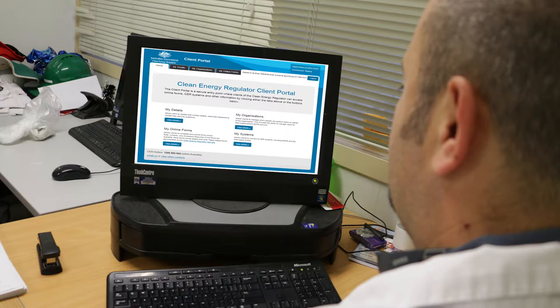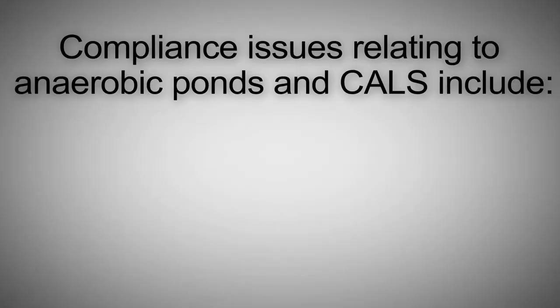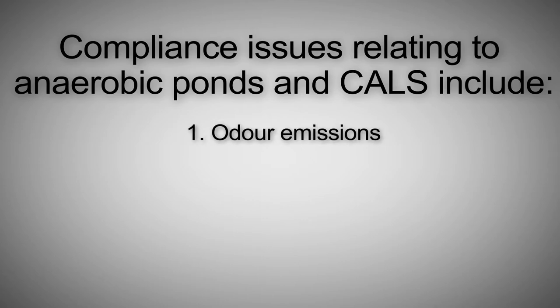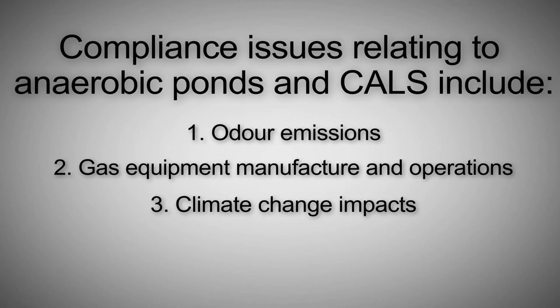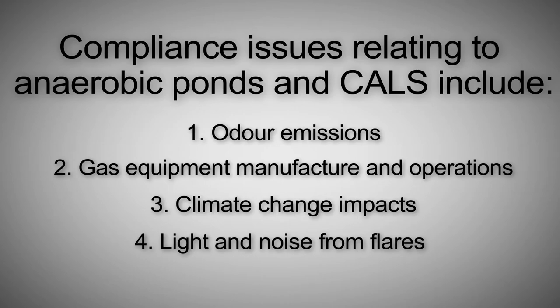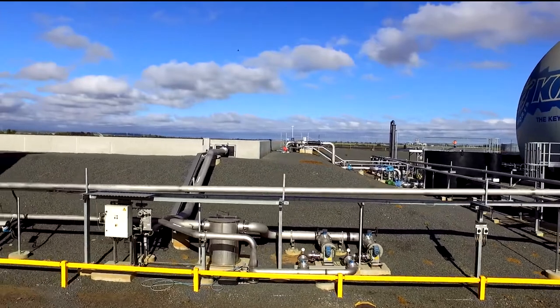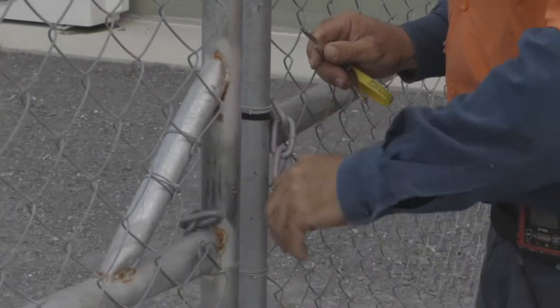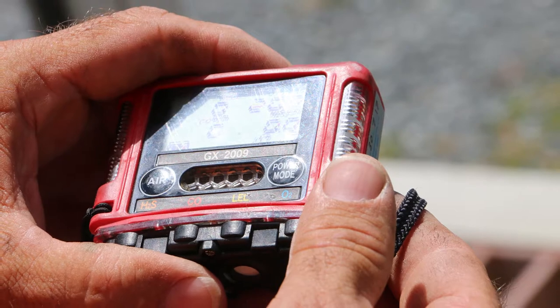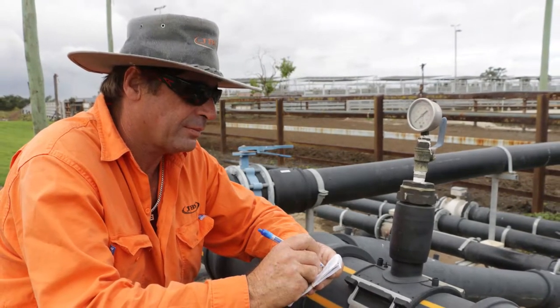For covered anaerobic lagoon systems, an additional layer of regulatory impact arises from the capture and use of the biogas. This involves compliance issues relating to various state-based agencies concerned with odour emission requirements, gas equipment manufacture and operation requirements and climate change impacts. There may be other compliance issues with flare operation, such as light or noise emissions. Finally, there are significant health and safety concerns with anaerobic ponds, whether naturally covered or as covered systems. These concerns relate to the potentially toxic nature of gases produced, in particular hydrogen sulphide and the flammable or suffocating nature of biogas. Personnel working on or near biogas capture, storage or combustion technology should refer to AMPC's biogas capture, storage or combustion manual and associated training material for guidance on operator safety.